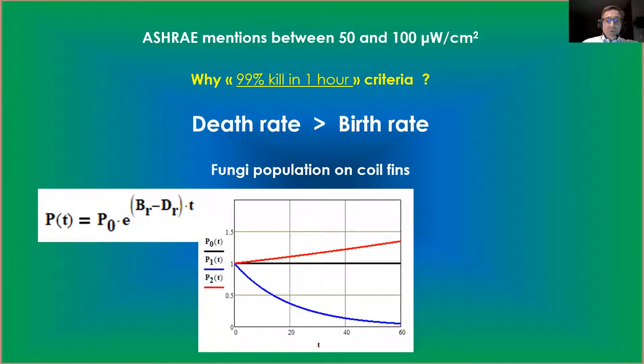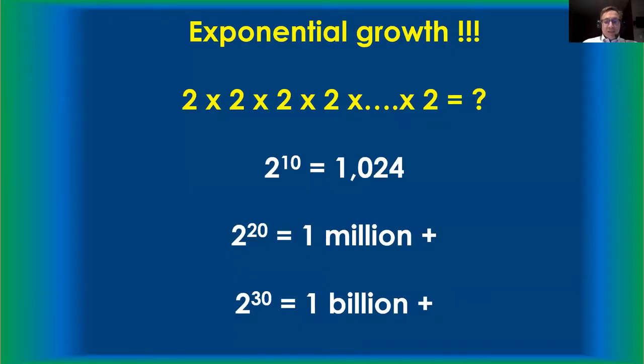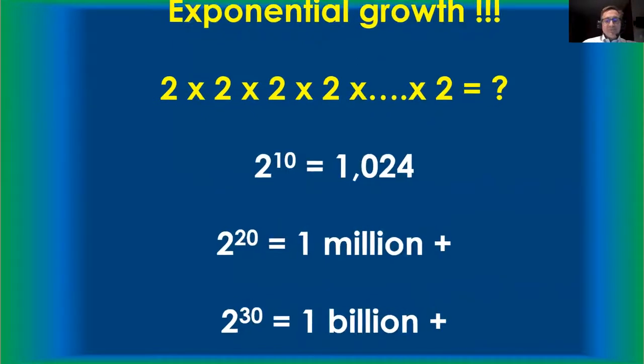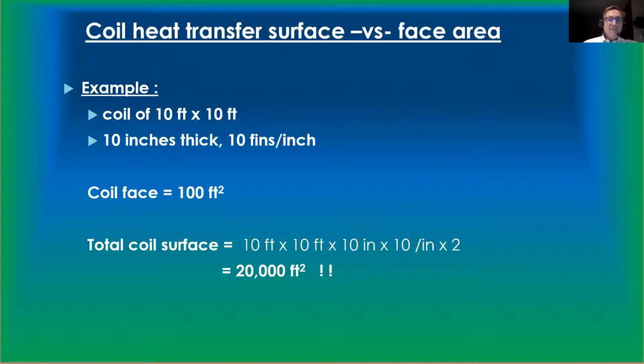We have a negative exponential and it dies out. Now it's a bit tricky with coils, because coils have a certain number of fins per inch and a certain thickness, so the exponential growth inside can be pretty dramatic. I'll show you after this. This is the inside of a coil that looks 10 feet by 10 feet, 10 inches thick, with 10 fins per inch. I use a simple math to show the idea. With a coil face that looks like 100 square feet, in fact the total inside surface is more like 20,000 square feet. A coil is a huge surface to cultivate molds, and it's inside.